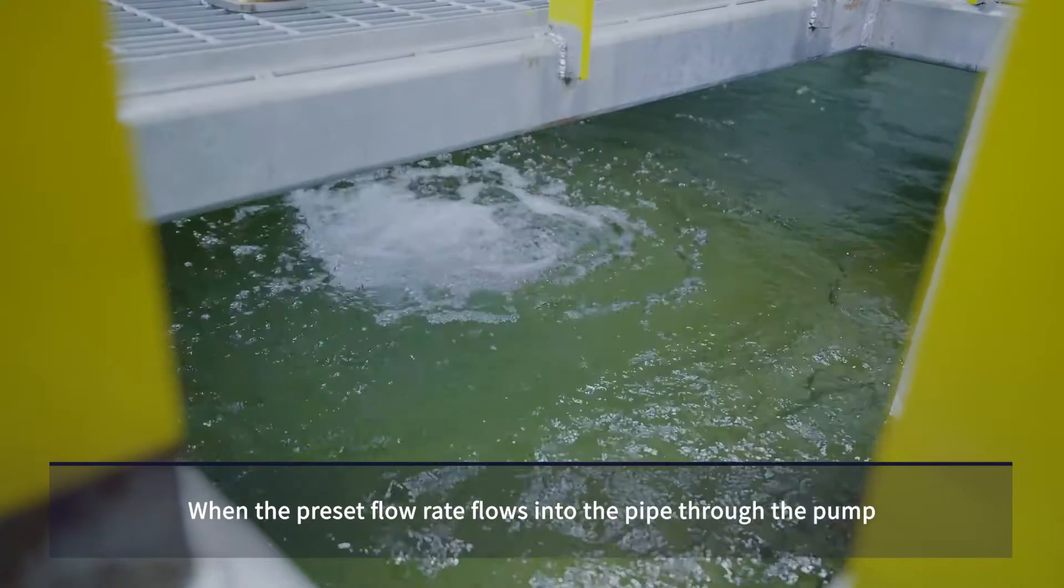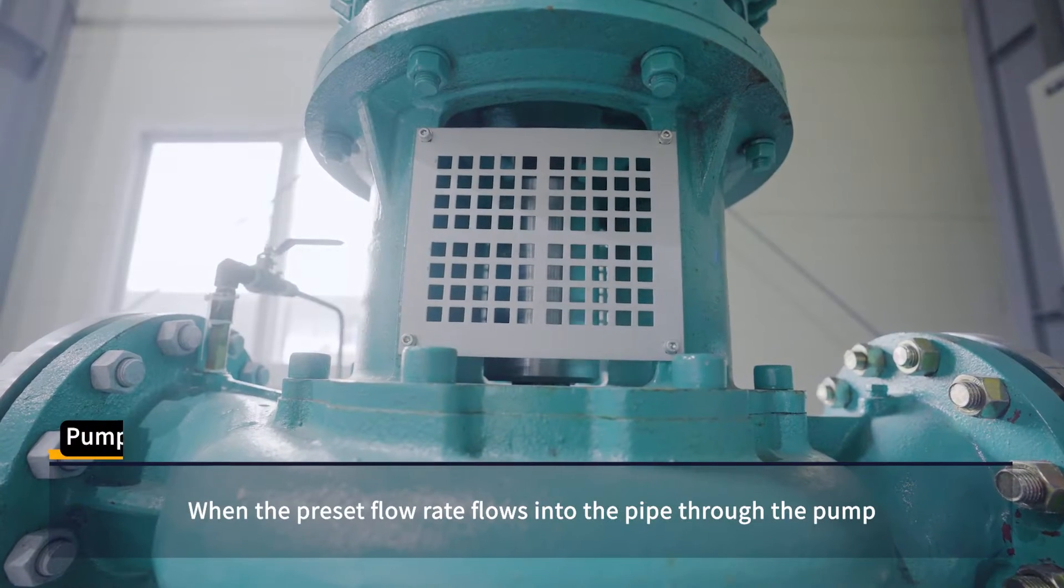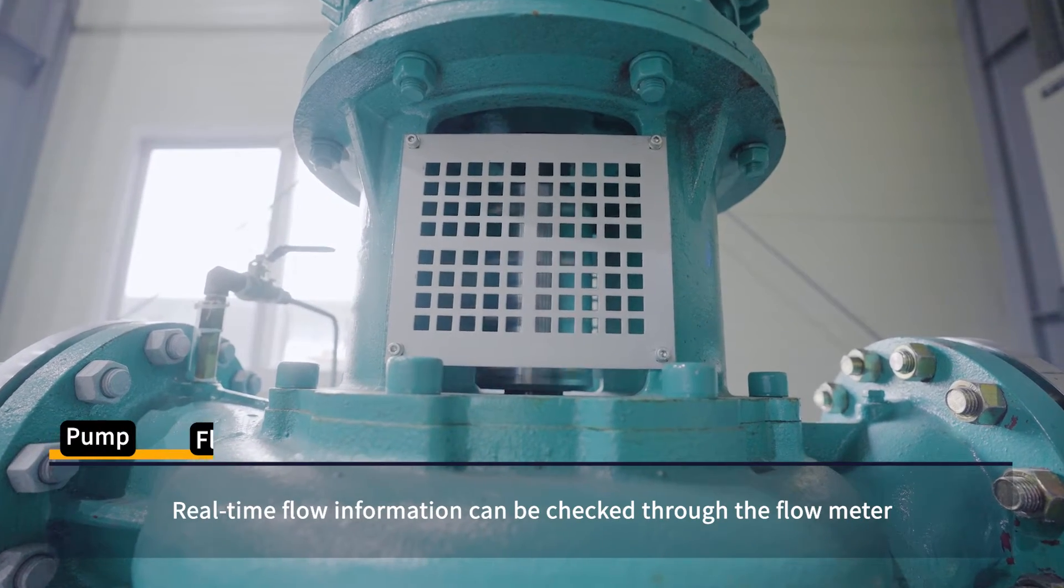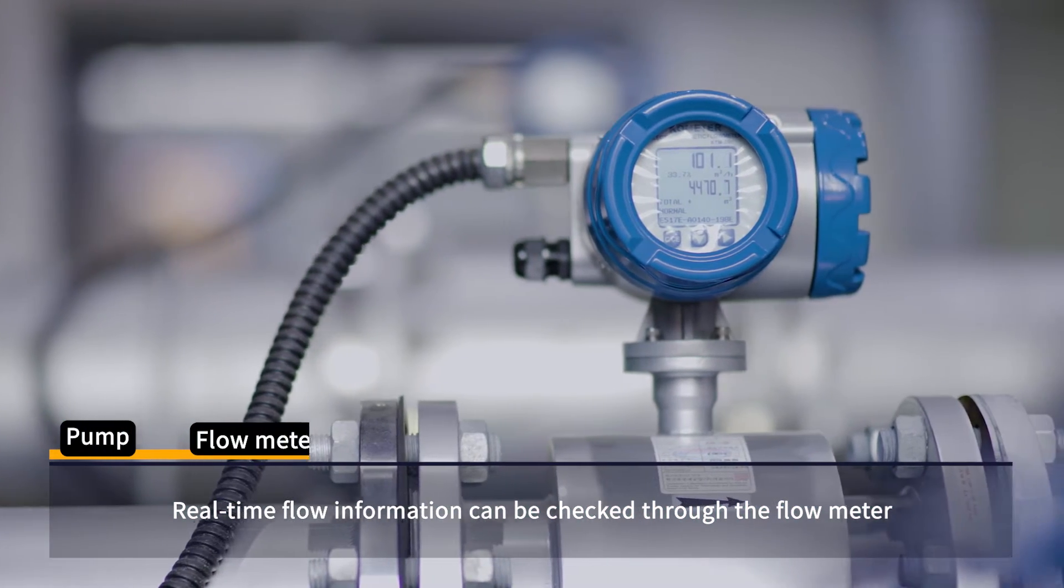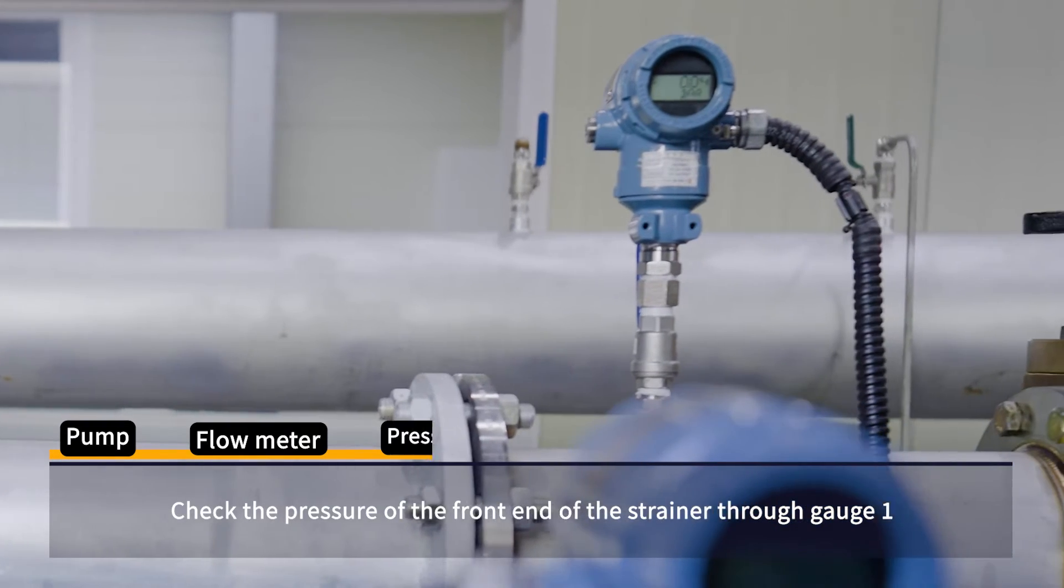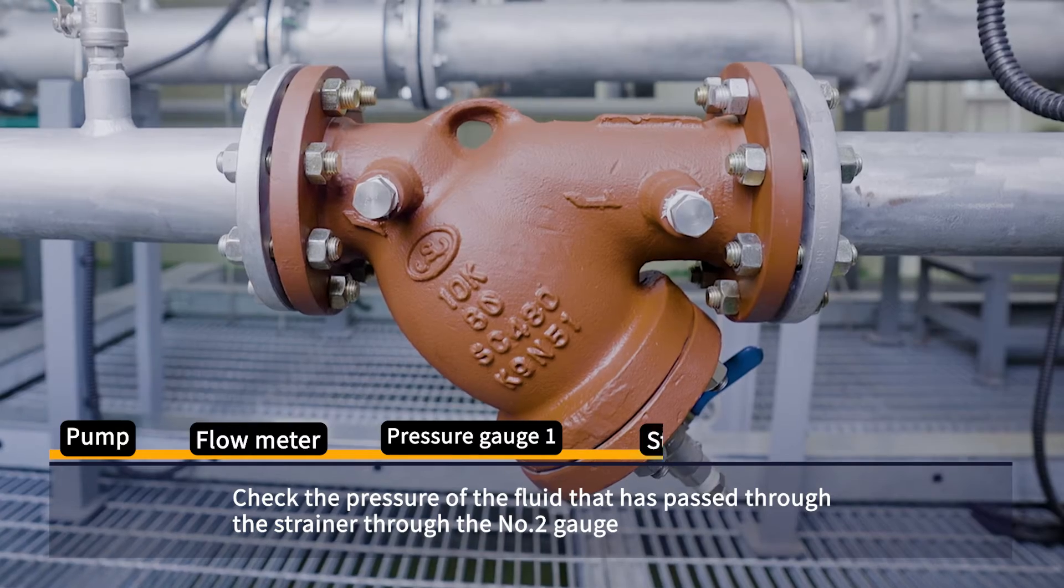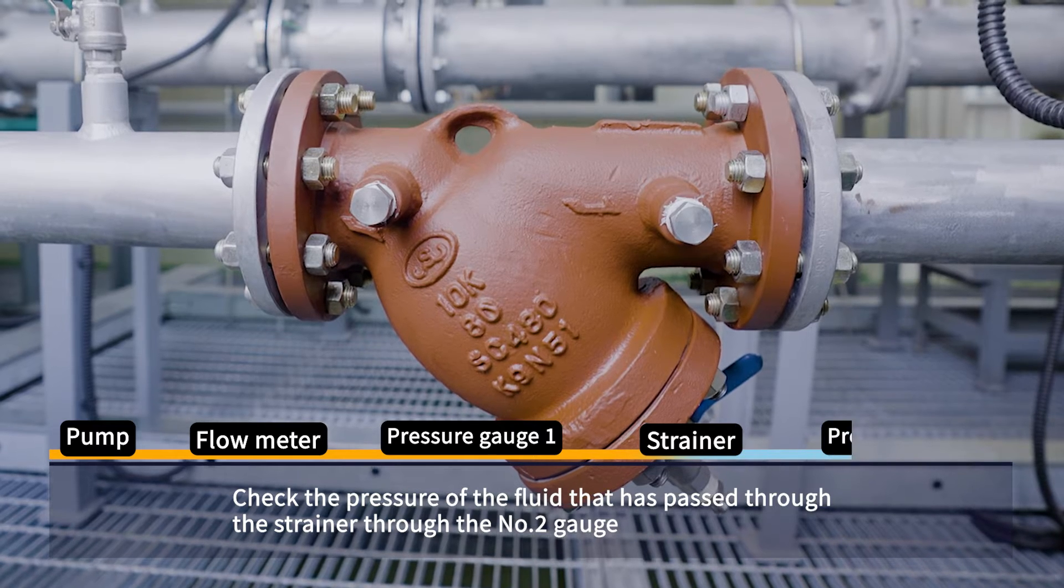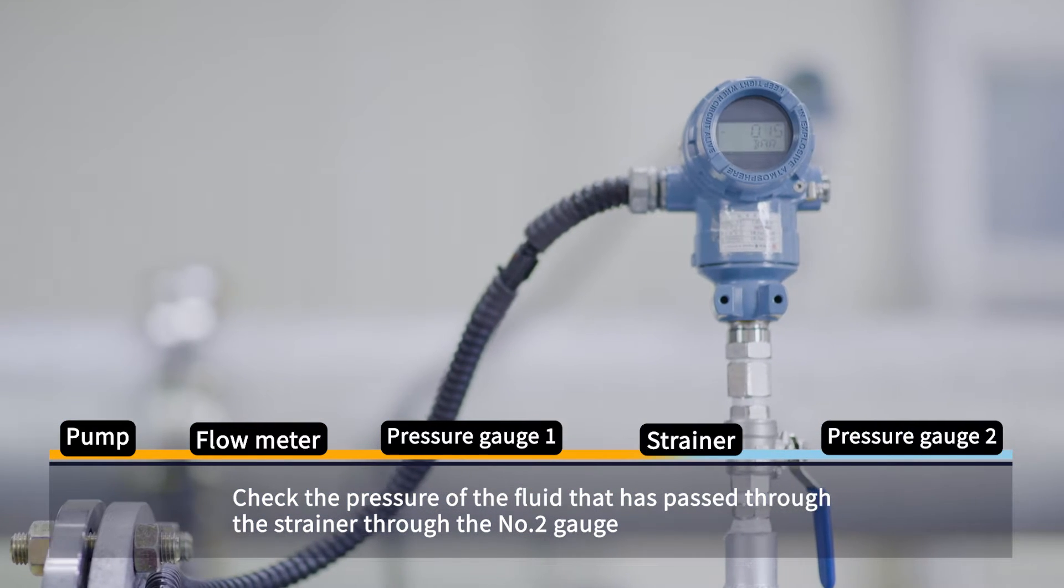When the preset flow rate flows into the pipe through the pump, real-time flow information can be checked through the flow meter. Check the pressure of the front end of the strainer through gauge 1. Check the pressure of the fluid that has passed through the strainer through the number 2 gauge.